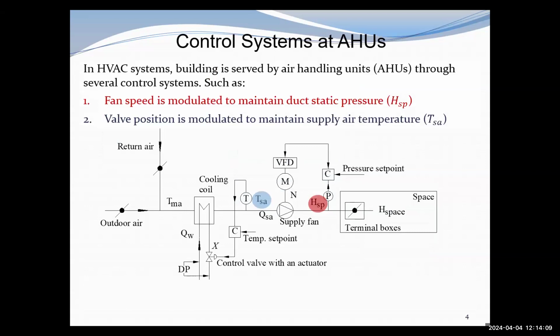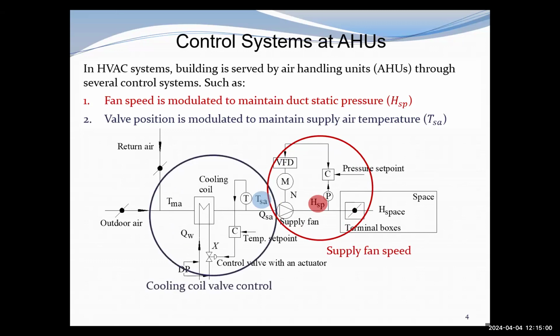In the HVAC systems, the air handling unit is a component that serves our buildings. In the air handling unit, the return air and the outdoor air are mixed in the mixing air chamber, and then the chilled water running through the cooling coil cools down the mixed air, and then the supply fan delivers the supply air to the space to cool it down in summer. The control loops at the air handling unit include the supply fan speed control. For the supply fan speed control, the fan speed is modulated to maintain the duct static pressure. Another one is the cooling coil valve control. For the cooling coil valve control, the valve position is modulated to maintain the supply air temperature.